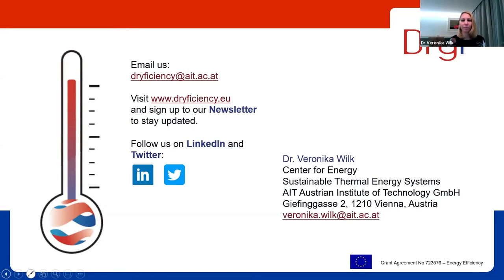Oh, good. Thank you. And any comments on the reliability of the heat pumps during the trials? Did you have a few surprises and a few operational issues there? I was smiling when reading that. Yeah, there were bugs and issues, as you always have when you operate an industrial plant. It was very interesting to find out that we had those bugs and issues not really related to the high temperature application, but to normal equipment. So pressure sensors, water pumps, and those items.